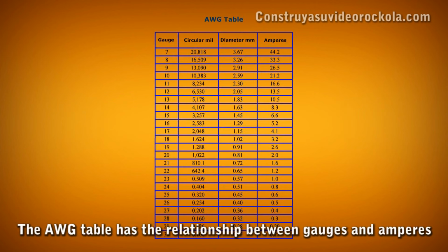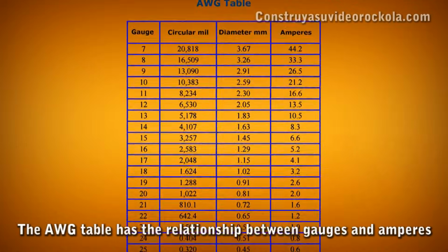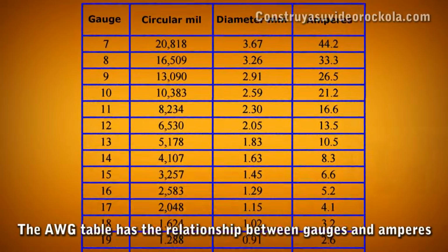Now we check the American wire gauge table that has the relations between the wire gauge and amperes. In our case, 10 amps is equivalent to 13 gauge. Remember that the toroidal transformer is more efficient, therefore we can use a gauge below without fear of overheating. So we'll use a 14 gauge wire for the primary winding. If your country's public network delivers 220 volts, then the gauge of the wire for the primary winding will be 16 or 17.